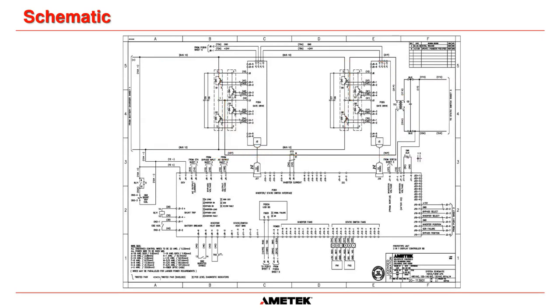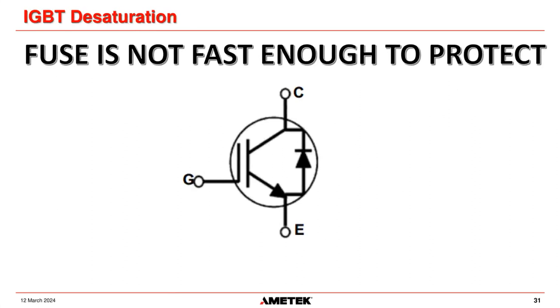And then when we do it the other way around and we turn this one on and this one on, power comes from the DC down through here, down to this point here, which then goes up and it makes that side of the transformer positive. And then we go down here through that IGBT back to the negative, and that makes that side of the transformer negative. So hopefully you can see that's a positive and the negative getting switched around with the H bridge.